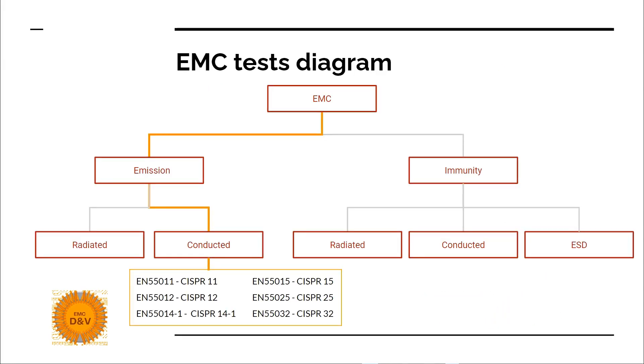This is a typical EMC test diagram that you will see in other materials. Electromagnetic compatibility tests are divided into emission and immunity. For emission, we have radiated emission and conducted emission. For immunity, we have radiated immunity, conducted immunity, and ESD electrostatic discharge. Conducted emission is a type of emission test that is conducted.